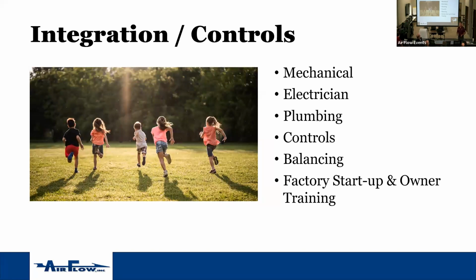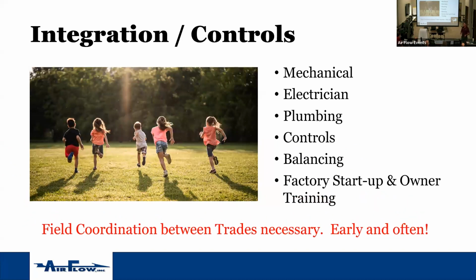The biggest hiccup we have on every single dust collection job that we see, it's not the install, it's not the ductwork, it's not the equipment, it's the controls. It's who does the wiring, where does the wiring come back to, what terminal do I land it on, how do I control it, I'm getting an error code here, how do I fix it? And the biggest thing we say is the field coordination between the trades should start right when POs are let. We will usually offer a couple of site visits and a couple of meetings just to get everybody on the same page.